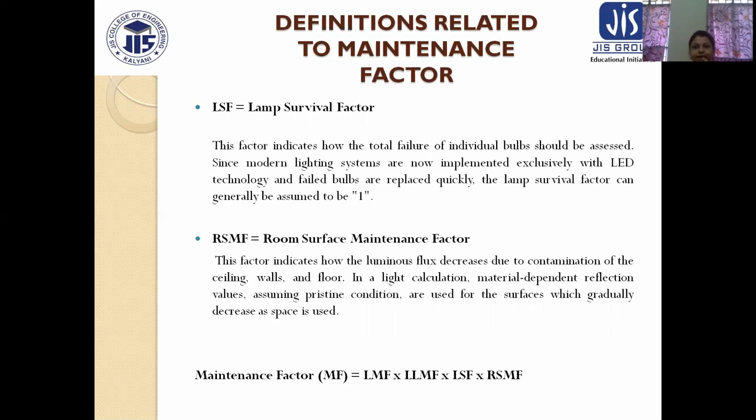Okay. Next, RSMF, room surface maintenance factor. This factor indicates how the luminous flux decreases due to contamination of the ceiling, walls and floor. In a light calculation, material dependent reflection values, assuming pristine condition, are used for the surfaces, which gradually decrease as the space is used. So maintenance factor equals LMF times LLMF times LSF times RSMF.